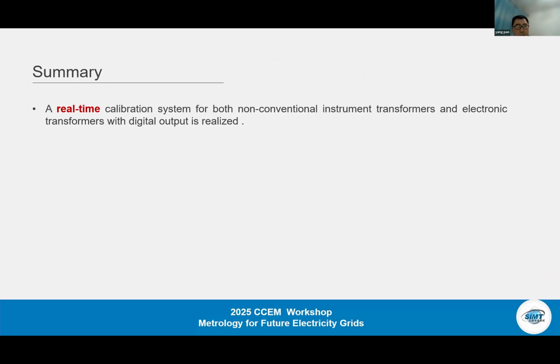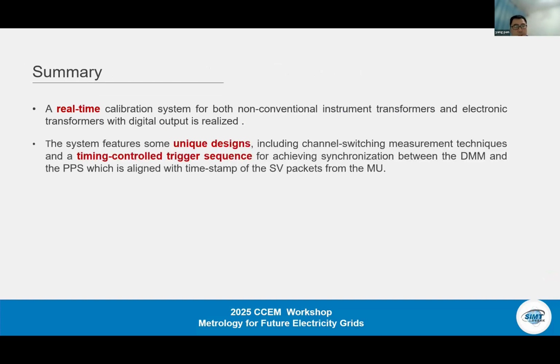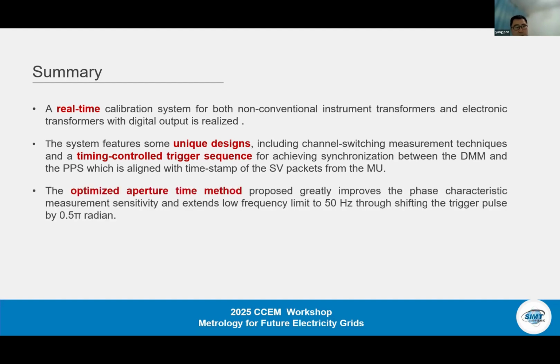So, summary. The real-time calibration system for both non-conventional instrument transformers and electronic transformers with digital output is realized. The calibration system includes the channel switching measurement techniques and timing control of the trigger sequence for achieving synchronization between the DMM and the PPS, which is aligned with the timestamp of the SV packet from the MU. The optimized aperture time method proposed greatly improves the phase characteristic measurement sensitivity and extends the low frequency limit to 50 Hertz.